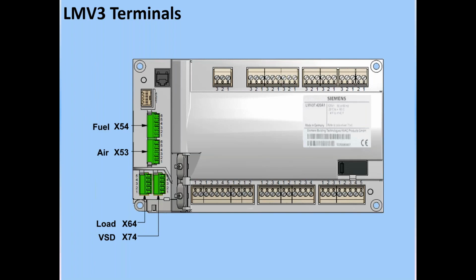Next, taking a walk around the LMV3, we have fuel terminals. X54 is the fuel, and actually X53 is the air. These are the actuator terminals for the SQM33 servos that go onto the unit. They are very dependent on which one you plug them into. So the plugs are identical, so you have to make sure that you plug the fuel into X54 and the air into X53. There is no addressing or any such feature on the SQMs, so you have to be very careful when you plug them in.